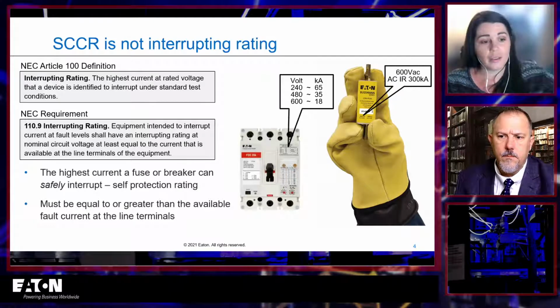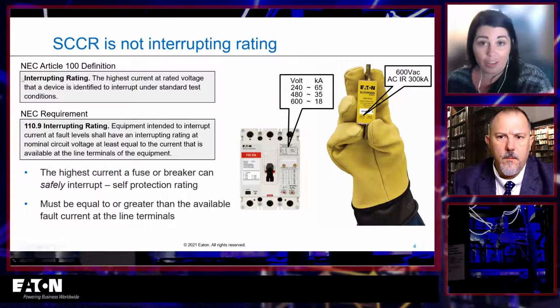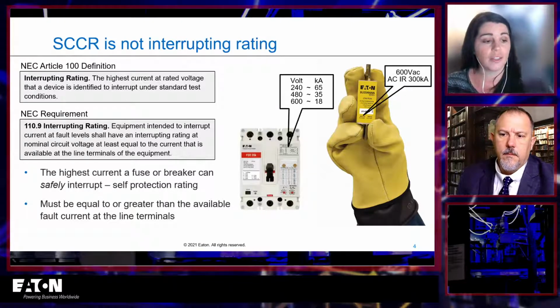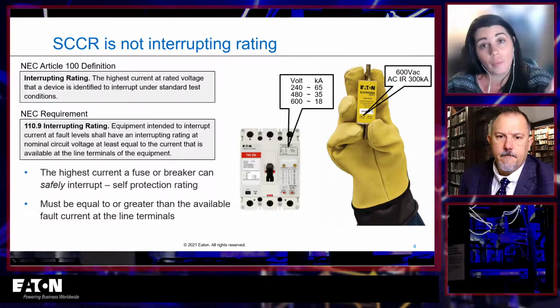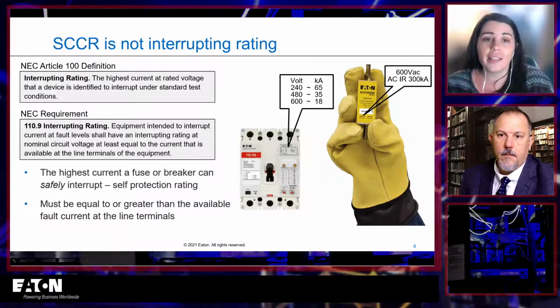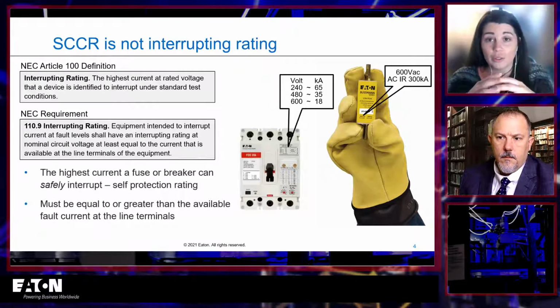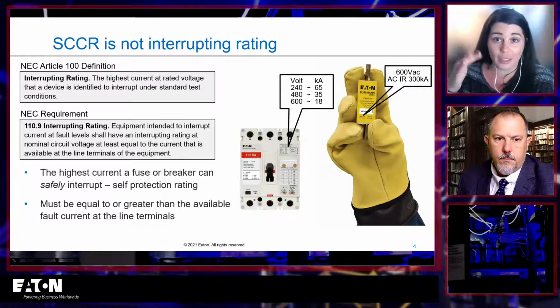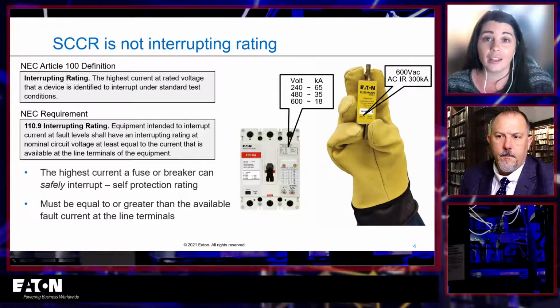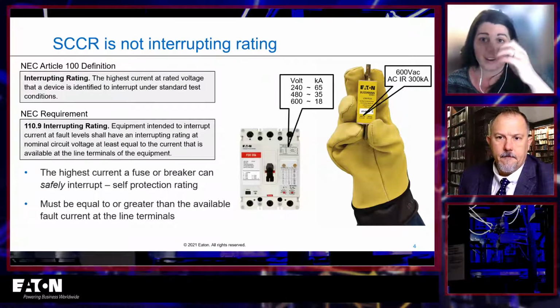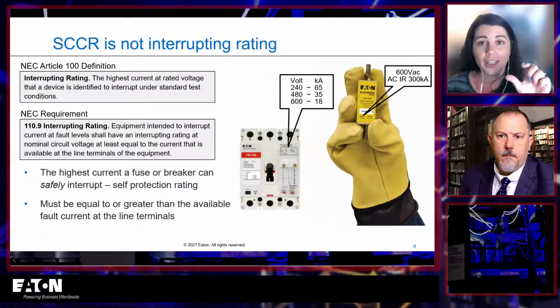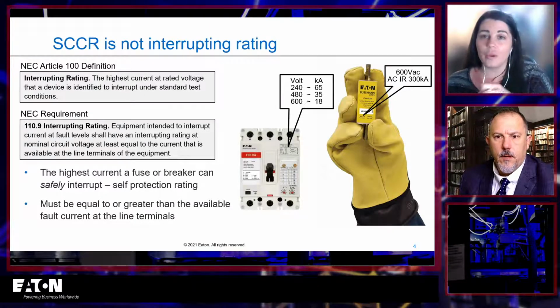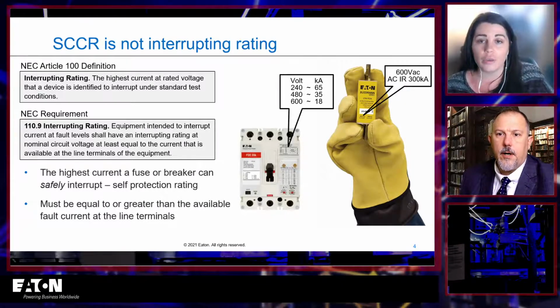Yeah, there is ambient changes, and again, it is usually to that overload region because that's where it's the most sensitive. High speed fuses are more sensitive than a normal UL low voltage fuse, and medium voltage fuses can be a little more sensitive as well to it. But yeah, they exist. There are derating factors if you're in a higher temperature, and that makes sense, I mean, that fuse is just all based on a thermal principle. So if the inside of it is going to melt at a specific temperature associated with a specific overcurrent over a specific amount of time, and it starts out at a hotter temperature, then that is obviously going to change when it melts. Although I do think there's sort of a larger range of temperature where you don't have to derate until you do with a typical low voltage UL fuse.